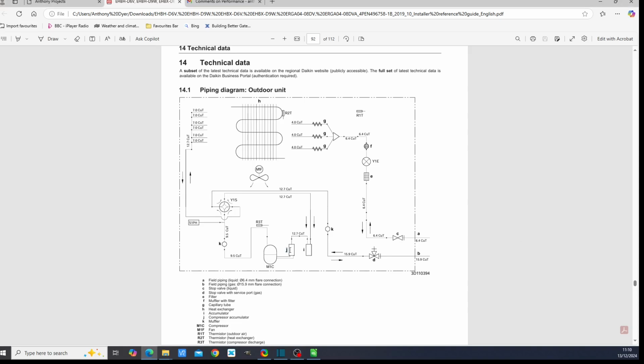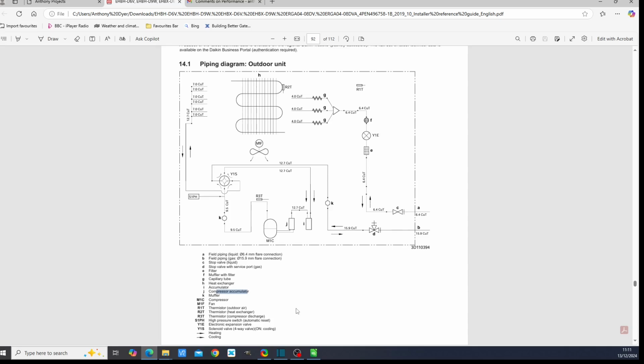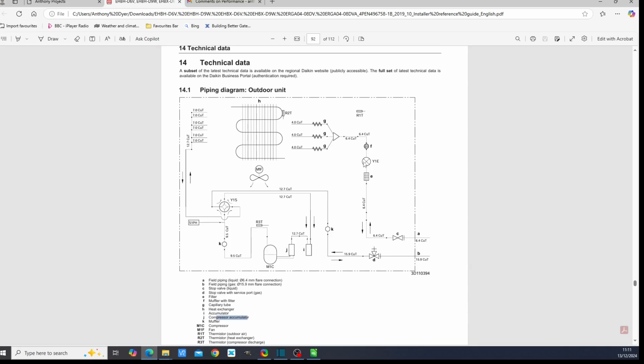If you look at Exhibit J, this is a compressor accumulator. This will provide a reserve of refrigerant needed to keep the flow of refrigerant going when your compressor is switched off. And the flow rate is going to be controlled by your expansion valve, which I think is Y1E. Is it Y1E? Yeah, electronic expansion valve. This will control your flow rate.